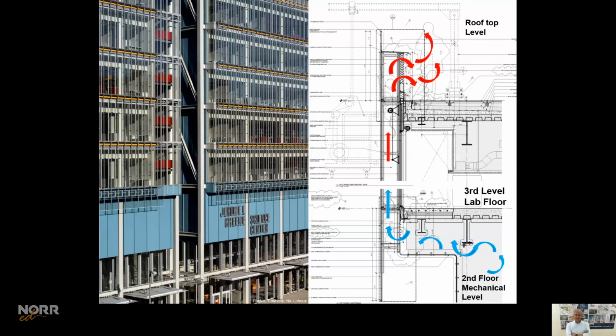Now I would like to explain how this active double skin works. We have a lab, and inside this lab we have 6 air changes per hour. The air goes through the mesh from the lab space to the HVAC system, where it's filtered 3 times and dehumidified. It's very, very clean air. What we usually do is blow this air out into the street.